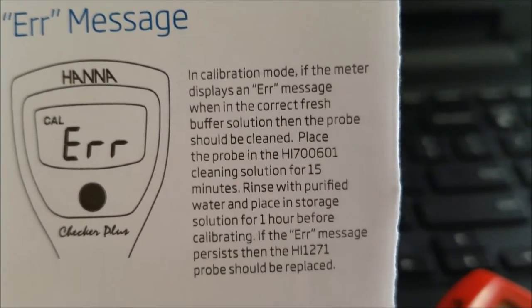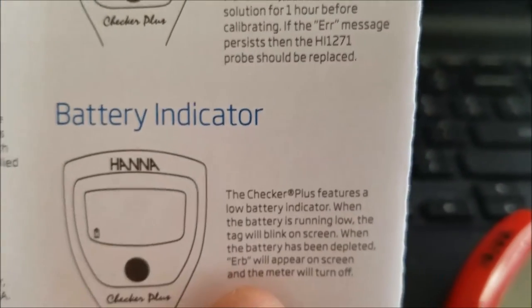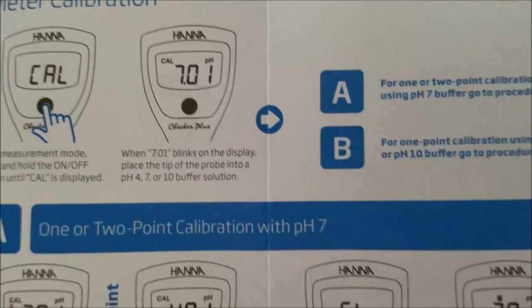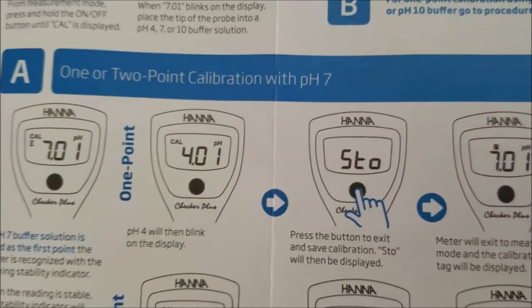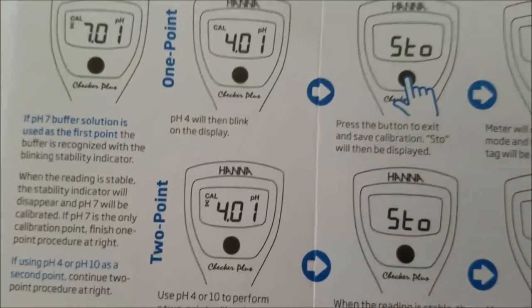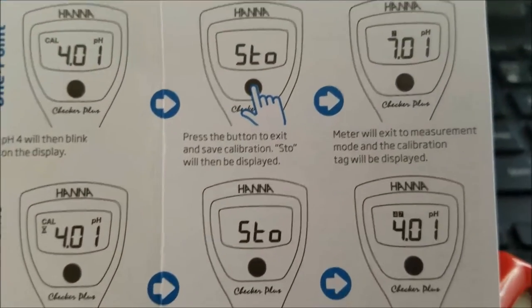As far as the instructions go, when you open them up you're going to see care and maintenance, warranty information, and recommendations for users. The first bit of information is the auto-off feature — the Hanna Checker pH probe has an auto-off you can set to 60 minutes, 8 minutes, or manual. To clear the calibration, on the screen where you have the off function, hold it until CLR is present, then hit it and it will clear any prior calibration. There's also an ERR explanation and a battery indicator. Opening the instructions fully folded out clearly shows you how to calibrate your meter — it shows how to hit calibration, it starts flashing 7.01, and then you determine whether you're going to do a one or two-point calibration.